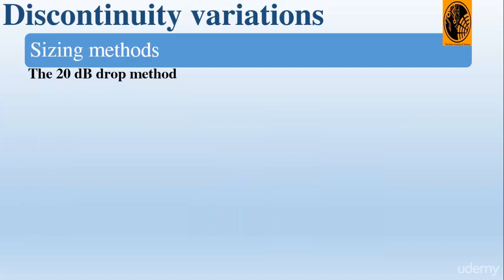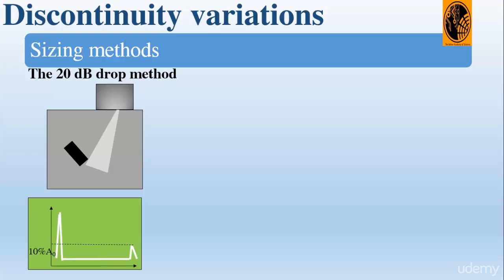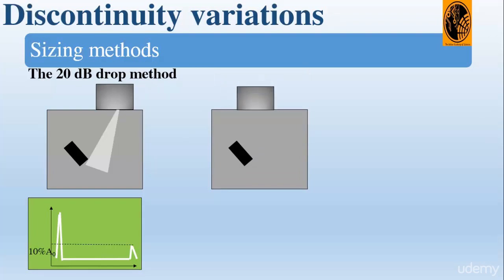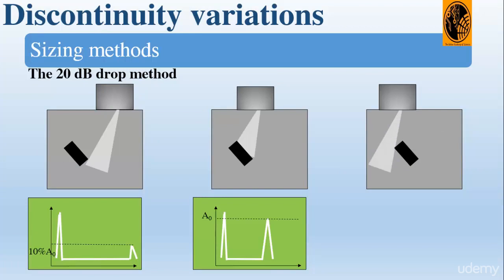Now let's see the 20 dB drop method. We can use a beam plot to find the edge of a defect by using the edge of the sound beam. If we know the width of the beam at a certain distance from the crystal, we can mark the distance across the defect from where the extreme edges of the beam touch each end of the defect, then subtract the beam width to get the defect size. When the signal from the defect drops by 20 dB from its peak, we judge that the edge of the beam is just touching the end of the defect. The peak of the defect is normally taken as the last peak on screen before the probe goes off the end of the defect, not necessarily the maximum signal from the defect.